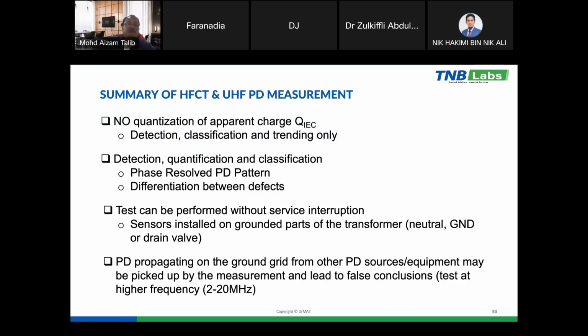So, a summary of the non-conventional PD measurement. We cannot quantify the apparent charge, so it is more for detection and trending purposes. And then through this PRPD pattern, we are able to classify the fault. The advantage is the test can be performed without service interruption. We do not need to shut down the transformer, cable or switchgear. We just put the sensor, and then it will pick up the PD signal.